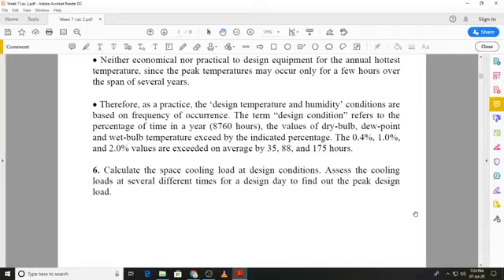Similarly, we can consider a frequency of occurrence of 1% or 2%. If we select a frequency of occurrence of 2%, it means that in a year, out of 8,760 hours, only 175 hours are such that our plant is not able to fulfill the load, that the load exceeds the design load. But it is possible, it's not necessary that will happen. And that is the practice. And when we look at the climatic data sheet, you will see that the outside design conditions can be decided based on these frequency of occurrence figures of 0.4, 1 and 2%.